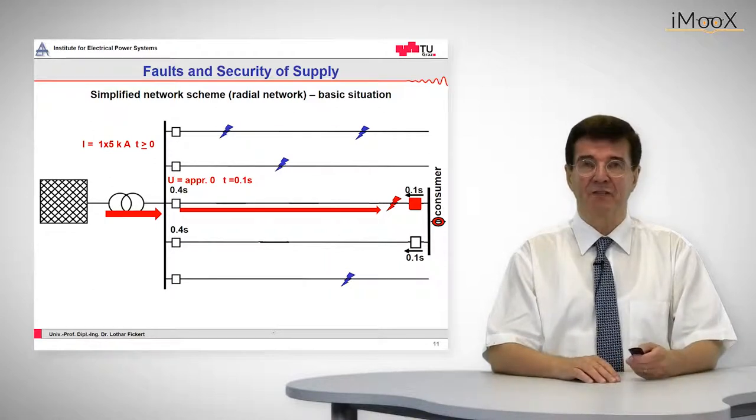So the one with the right direction will trip out. That's given here and we have the standard situation of a radial feeder fault which is cleared after 0.4 seconds by the overcurrent time protection.